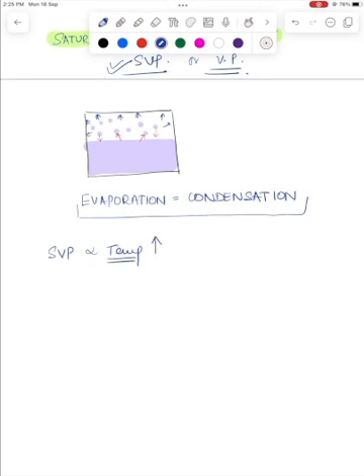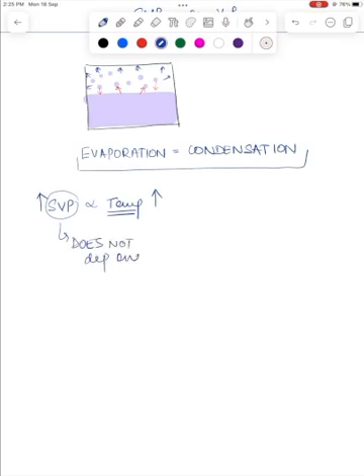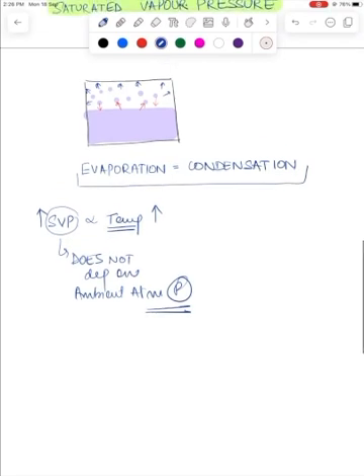At this point of equilibrium, the pressure exerted on the walls of the container by the molecules of the volatile agent in the gaseous phase is known as its saturated vapor pressure, or simply vapor pressure. Saturated vapor pressure is a function of temperature — as temperature increases, the saturated vapor pressure will also increase — but it remains unchanged with changes in barometric pressure. So saturated vapor pressure does not depend on the ambient atmospheric pressure, and the saturated vapor pressure can also be thought of as the volatile agent's partial pressure.